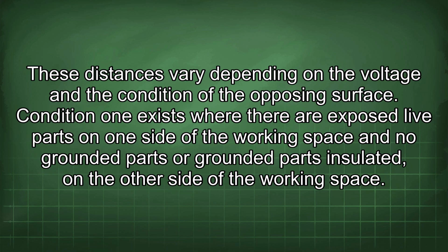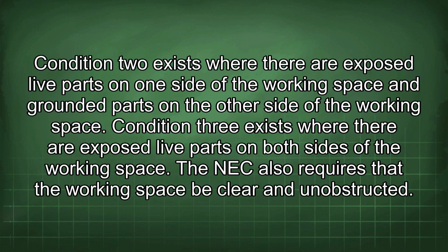Condition 1 exists where there are exposed live parts on one side of the working space and no grounded parts, or grounded parts insulated, on the other side of the working space. Condition 2 exists where there are exposed live parts on one side of the working space and grounded parts on the other side of the working space. Condition 3 exists where there are exposed live parts on both sides of the working space.